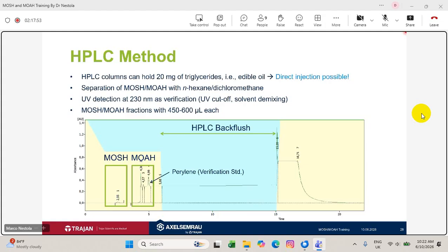Unfortunately, dichloromethane has a very low elution strength in normal phase. So when you have very highly polar compounds, you can flush for 10 hours, but you cannot remove those compounds. Typically, what you do in this case is take the column out of the instrument and connect it, in the best case, to another pump, where you have something like methanol, ethanol, isopropanol, because these solvents are much more polar, and you are removing compounds from it.